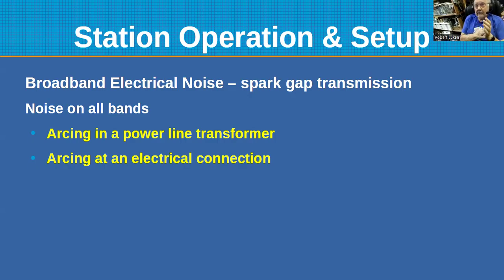You can get that from insulators arcing over on power lines. The transformers are on the insulators on the lines, particularly around here close to the coast where you get a lot of salt. That's why they go around and wash them off, because that salt causes them to arc over and generate a lot of broadband noise. Electrical connections that are not tight, where you can have some arcing, do the same sort of thing.